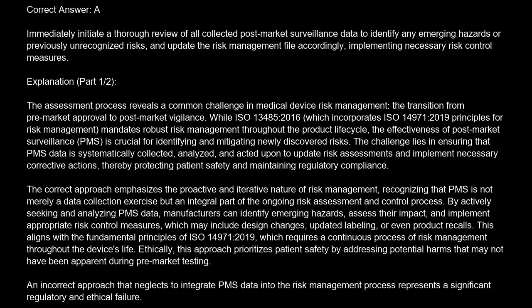The correct answer is A. Immediately initiate a thorough review of all collected post-market surveillance data to identify any emerging hazards or previously unrecognized risks and update the risk management file accordingly, implementing necessary risk control measures. Explanation. The assessment process reveals a common challenge in medical device risk management: the transition from pre-market approval to post-market vigilance.